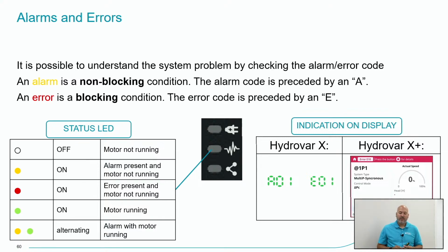They're going to be shown on the LED as a yellow flashing light and is a non-blocking condition. So what we mean by non-blocking is it's not going to stop operation of your system or your pumps or motors. What's going to happen is it's just going to notify you something is wrong and you need to take a look at it, but everything as far as operational standpoint is still going to remain active. An error is a blocking condition, so that is more critical. That is actually going to shut down your unit and need some manual intervention to fix it before it's up and running again.